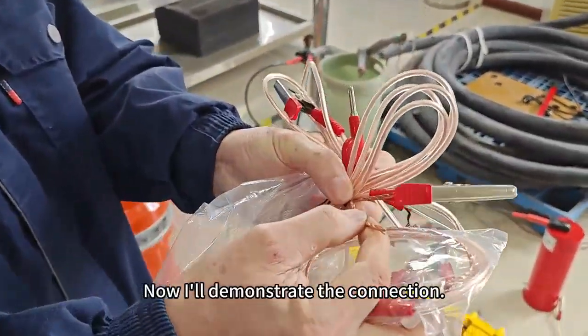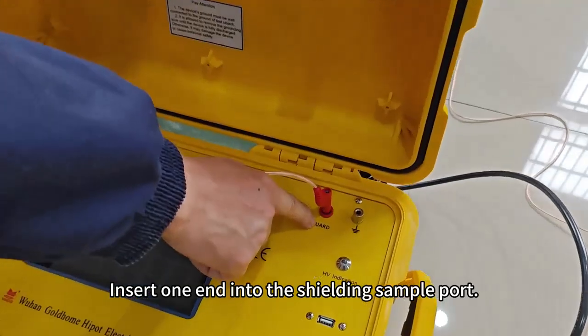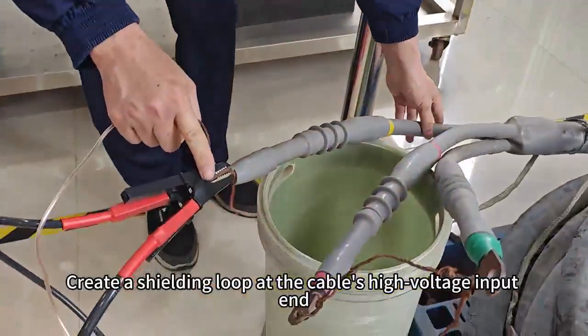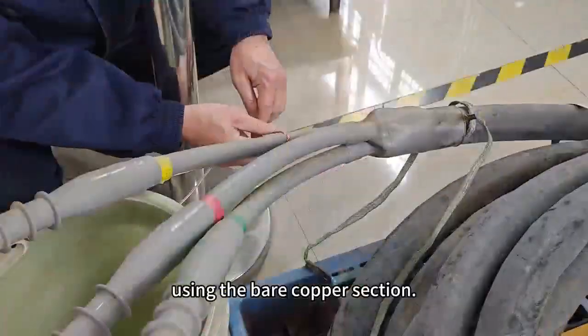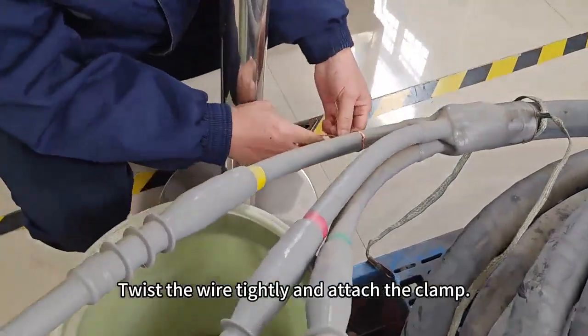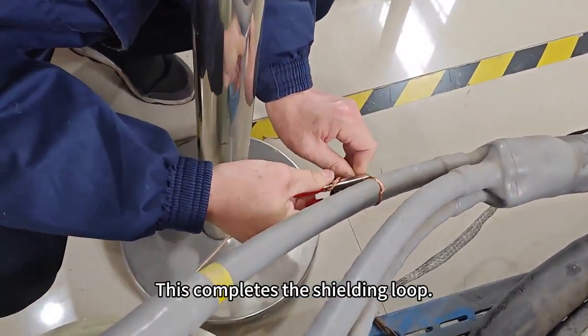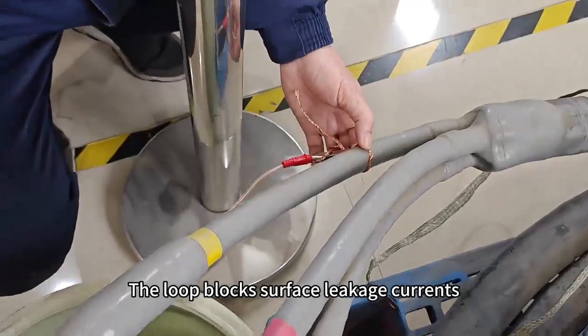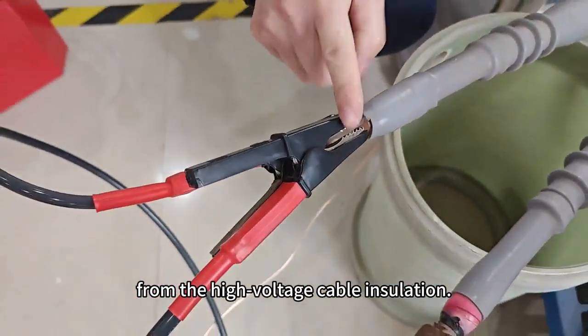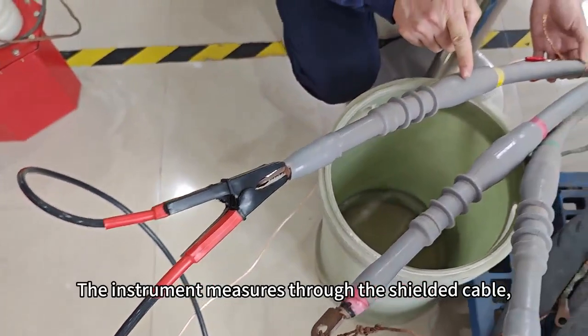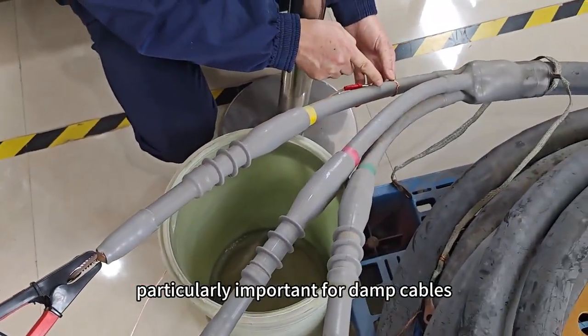Now I'll demonstrate the connection. Insert one end into the shielding sample port. Create a shielding loop at the cable's high voltage input end. Using the bare copper section, twist the wire tightly and attach the clamp. This completes the shielding loop. The loop blocks surface leakage currents from the high voltage cable insulation. The instrument measures through the shielded cable, particularly important for damp cables.